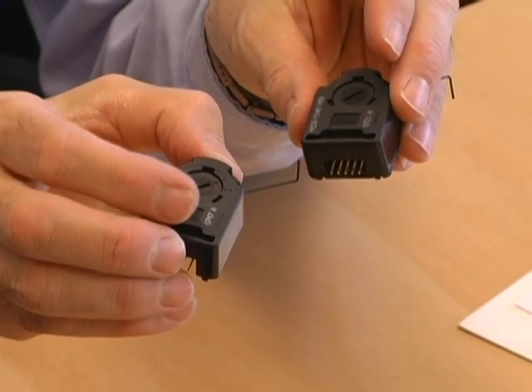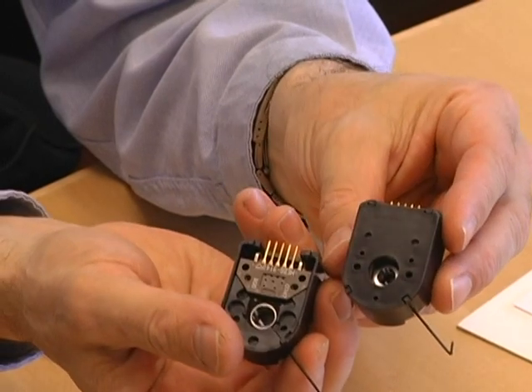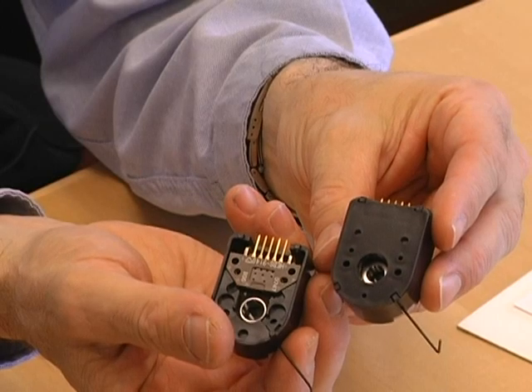The other most popular incremental encoder we make is the HEDS-5500-5600. Here's one example with the bottom plate removed so you can see the pieces, and also with the bottom plate on. This family is our most versatile and we have the most options available. These are used on motors typically over 40 millimeters in diameter, so they are physically larger. One of the advantages is you can get this in a whole range of resolution from 50 counts per revolution all the way up to 1,024. It also operates at 100 kilohertz. These come with either a metal code wheel or a mylar code wheel — the metal ones can handle higher temperatures, but if you want to go up to 1,000 or 1,024 counts per revolution, you go to the mylar code wheel, which has much finer resolution capability.